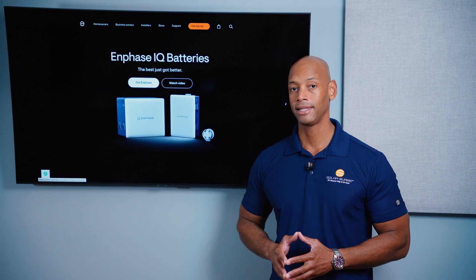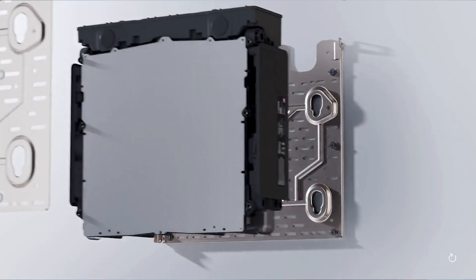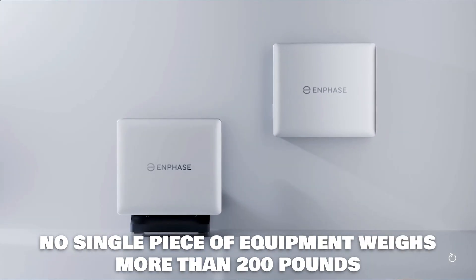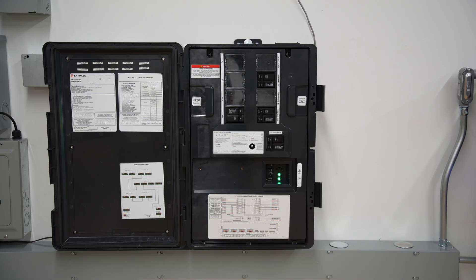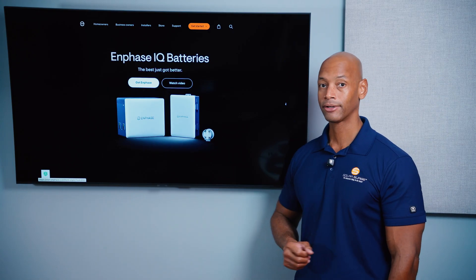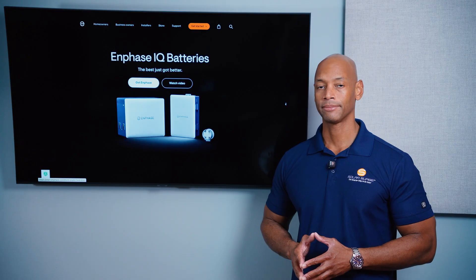In terms of ease of installation, I'm going to give Enphase three out of five points here. They have made some improvements in the battery design to make it easier to install. The 10 kilowatt hour battery is broken up into two separate five kilowatt hour modules, so no single piece of the system weighs more than 200 pounds, meaning the installation can be performed easily with just two technicians. They've also upgraded the Enphase Combiner 6C to basically eliminate the need for a separate system controller, which used to be their transfer switch. And as far as wiring the home for whole house backup, you can utilize the new Enphase IQ Meter Collar Adapter, so you don't have to wire your own critical loads panel or use a separate transfer switch.